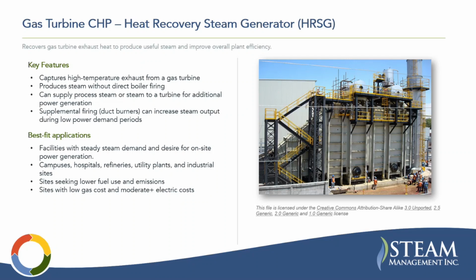You can use that steam for process loads or any kind of thermal loads, but also you could just send it to another steam turbine and generate more power and just increase the electricity output. But some key features here: captures high temperature exhaust from gas turbine, produces steam without direct boiler firing. Although I will say it's common to have duct burners in this section to supplement heat when the gas turbine doesn't have as much load, so you can still get your steam required from your HRSG.